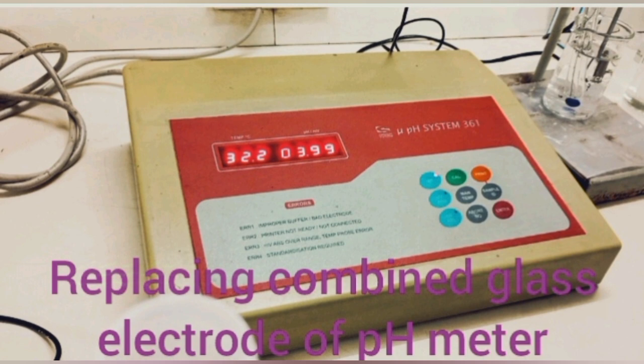But if you take care of this, it is advisable to change it within 6 months, but it depends upon the sample. Many scientists and people use a glass electrode for years together. It is not a bad thing, we can use it also, but we have to take care. Calibration must be done from time to time, buffer solution should be maintained, and the pH meter glass electrode tip should be kept inside pH 4 or 7.0 buffer, or if that is not available, you should simply keep it in distilled water, otherwise it will disturb your reading and put a question mark over the accuracy of your findings. So now we will tell you how to do the process.